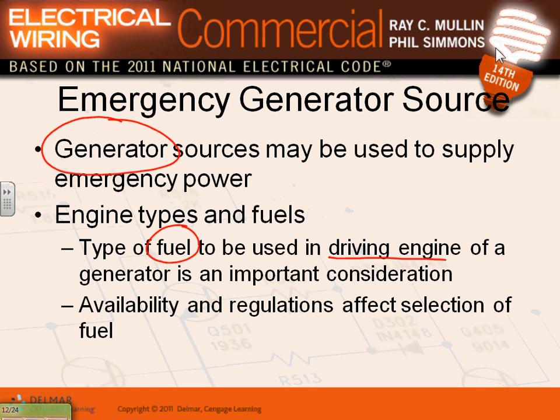Okay, regulations affect the selection of the fuel. I'm going to refer you to Jerry Bob's awesome presentation about the EPA requirement. It's on YouTube, EPA requirements for generators. Right now, guys, as Jerry said, unless your generator is an emergency generator, a legally required standby generator, or a COPS generator, these are all under the umbrella of required generators for hospitals, COPS systems, emergency, or legally required.